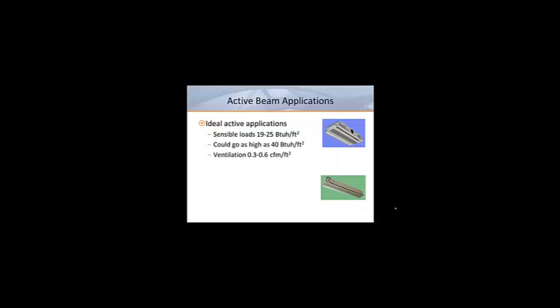Now let's take a look at active beam applications. It is much easier to find good applications for active beams because they handle both sensible and latent while addressing ventilation requirements. Generally speaking, they are best suited for spaces where sensible loads range from 19 to 25 BTUs per hour per square foot, but they have been successfully applied to handle up to 40 BTUs per hour per square foot. As far as air volume requirements, they are best suited to spaces requiring from 0.3 to 0.6 CFM per square foot. When applying active beams, the sensible heat ratio or SHR must be taken into account. This is defined as the sensible heat load divided by the total heat load. Of course, the total heat load is the sum of the sensible and the latent loads. In order to be suitable for active beams, the sensible heat ratio should be 0.7 or greater. In situations where latent loads are high, the sensible heat ratio will be lower and higher ventilation rates would likely make active beams a poor system choice.